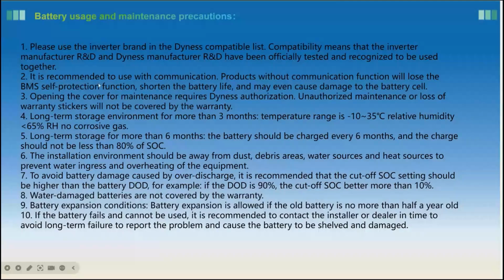Okay, the second is we recommend using the battery with communication. When you use communication, the battery BMS has its own protection logic. Without communication, the battery will lose the BMS protection, and you need to set the charge voltage, discharge voltage, cut-off SOC and cut-off voltage on the inverter. All the control will be on the inverter. Once the inverter malfunctions, the battery may lose protection.